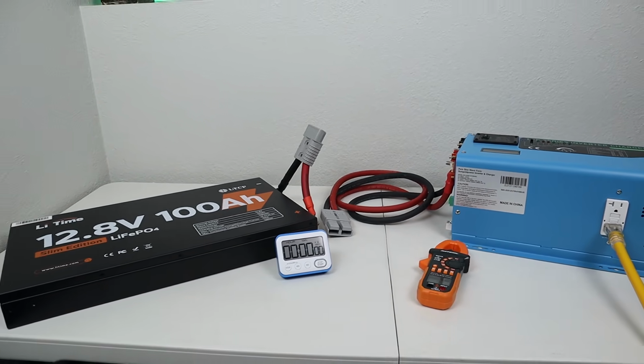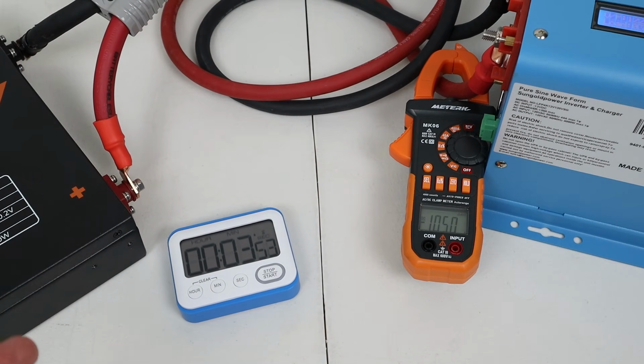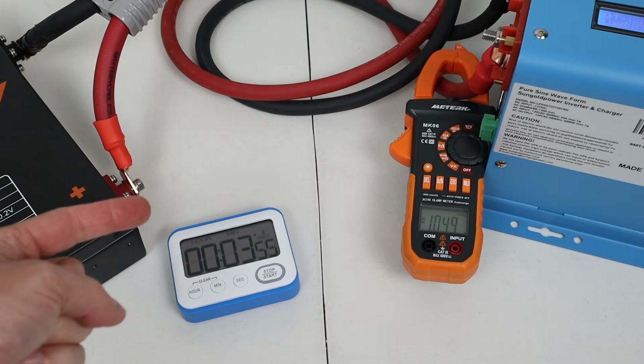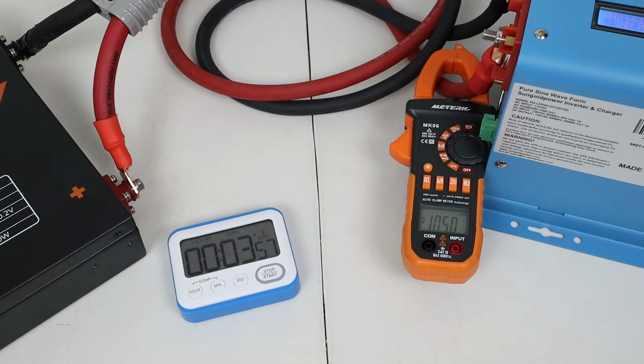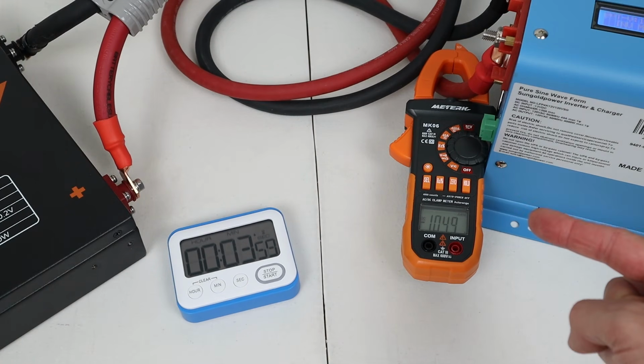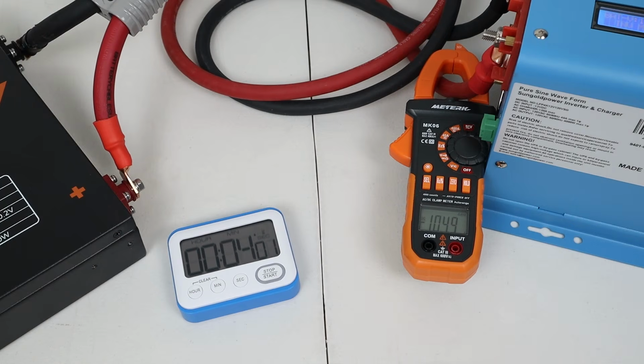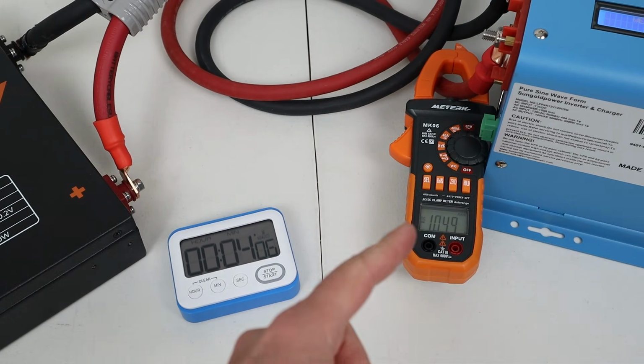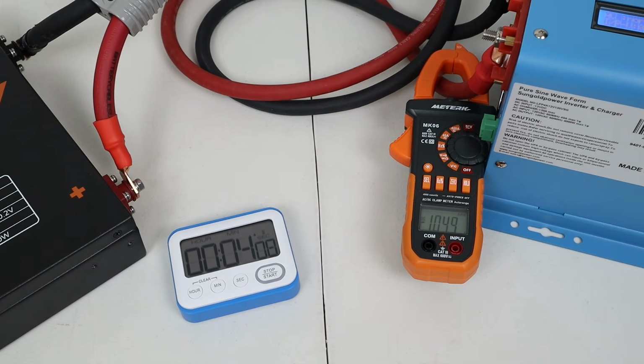Let's get started. So I've set up the 100 amp load on the battery. It's actually been going for almost 4 minutes now, and with my clamp meter here, you can see we're pulling right around 104.9 to 105 amps. It'll be interesting if it'll let us run just a little bit over 100 amps for 15 minutes. So I'm going to let the timer go, and we'll come back after 15 minutes and see what's up.